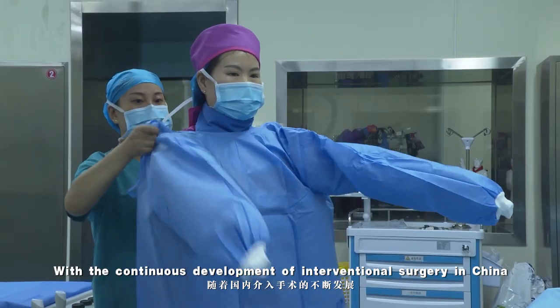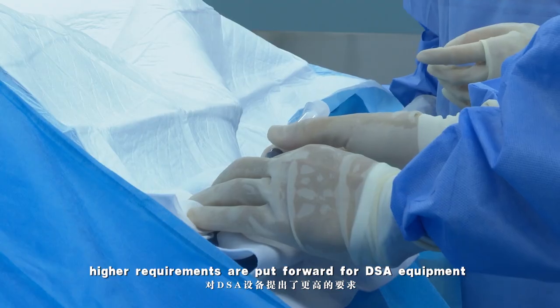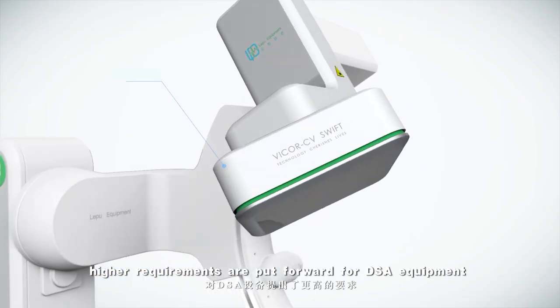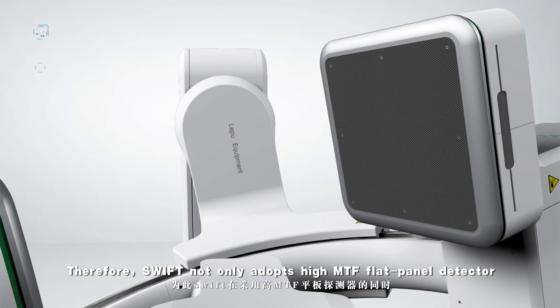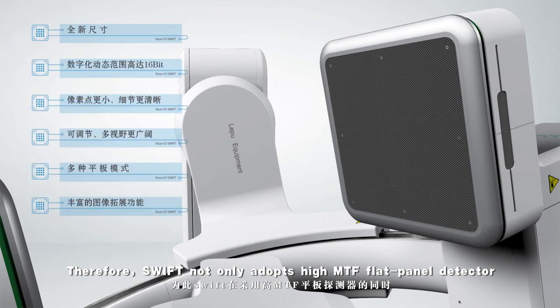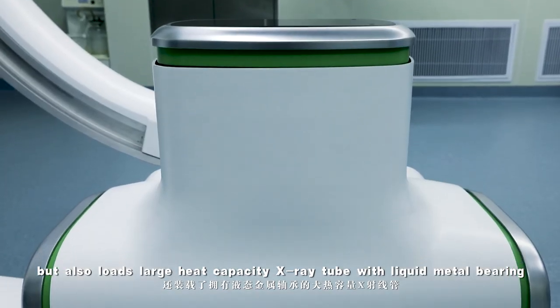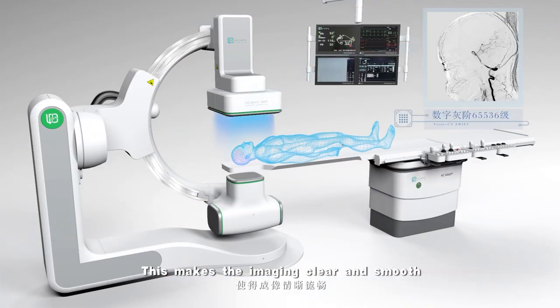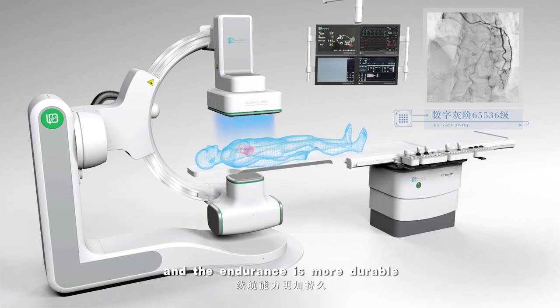With the continuous development of interventional surgery in China, higher requirements are put forward for DSA equipment. Therefore, the SWIFT not only adopts a high MTF flat-panel detector, but also loads a large-heat-capacity X-ray tube with liquid metal bearing. This makes the imaging clear and smooth, and the endurance more durable.